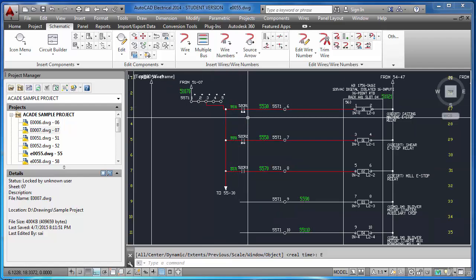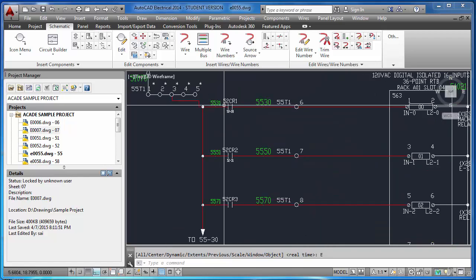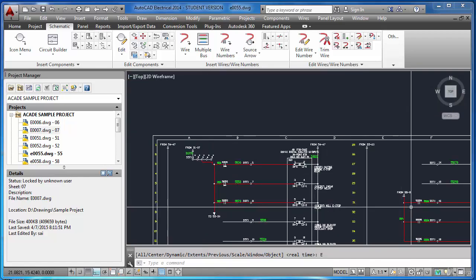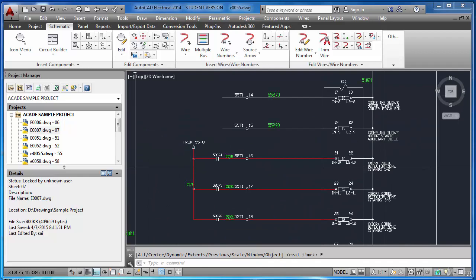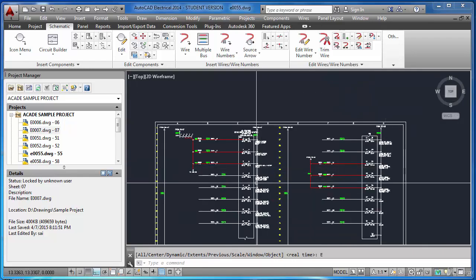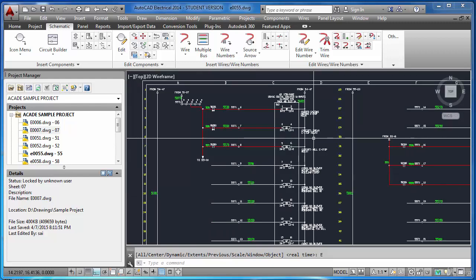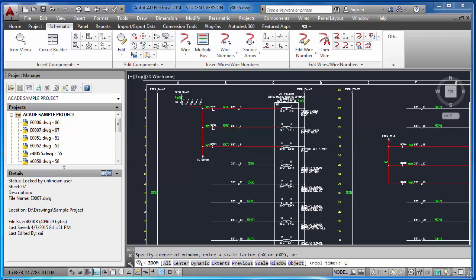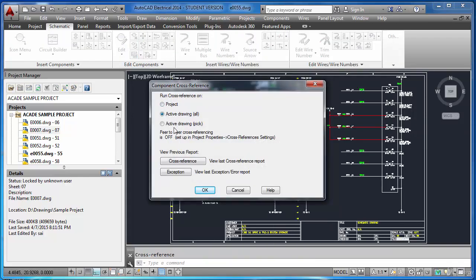So I am looping that supply through these relay contacts from one contact to another, and from here to here. In fact, if these IO list descriptions were here, I should not have used the source or destination arrow. I could loop it continuously. But this list is provided by the customer, so I cannot put it as per my fancy. So I have to follow some norms. So this is input. Using this component cross-referencing, we can do it. Okay, project.